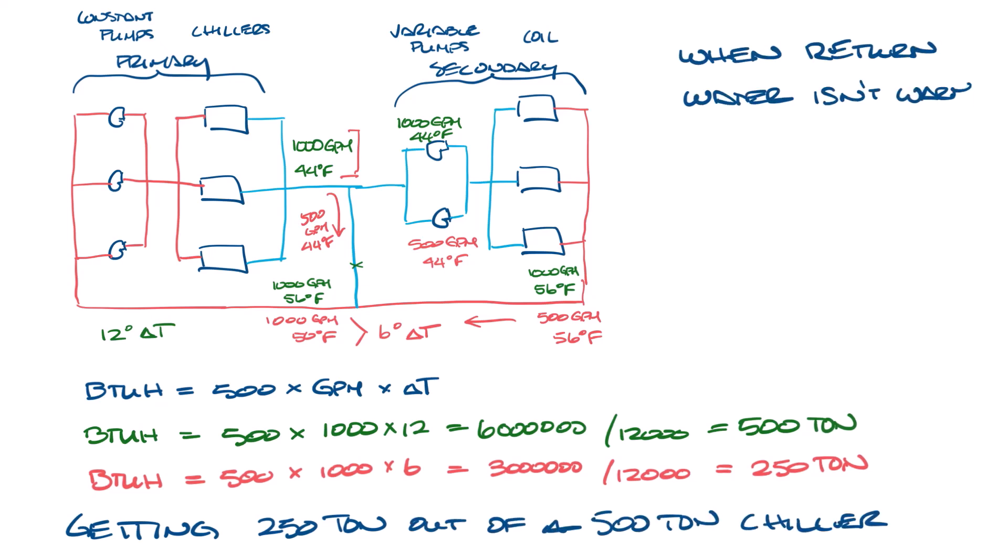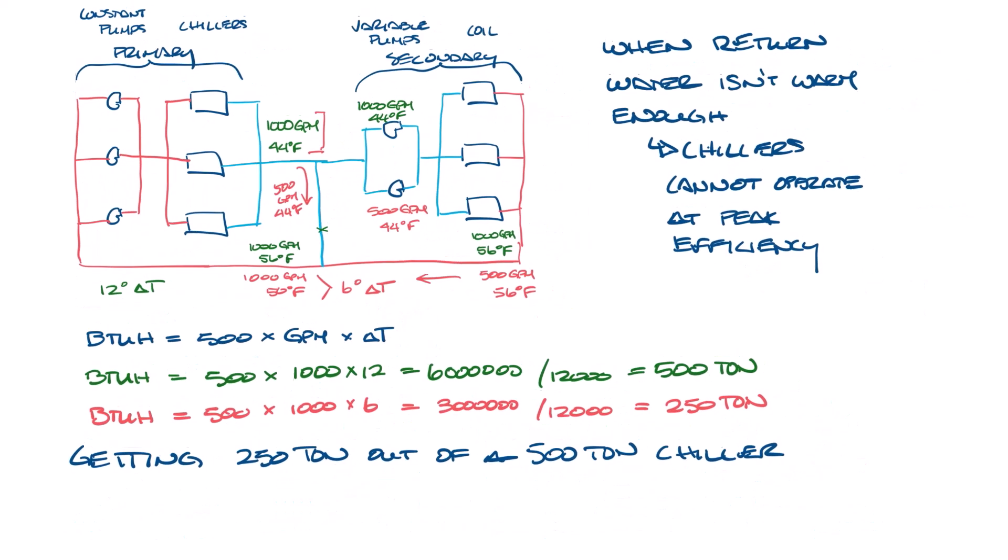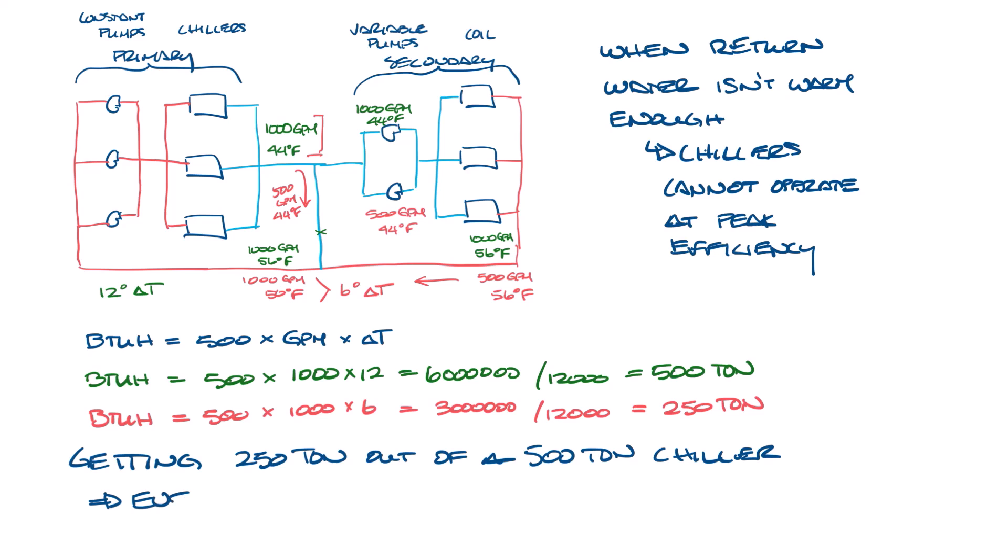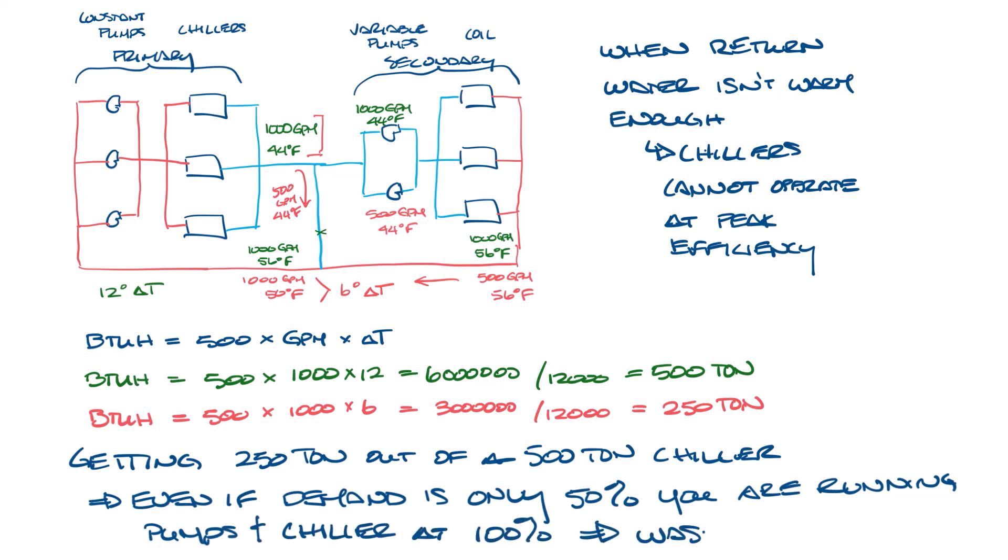When the return water isn't warm enough, chillers can't operate at peak efficiency. So even if the demand was such that you only needed 50% of the cooling, running the pumps and chiller at 100% for 50% load is not efficient. This wastes energy.